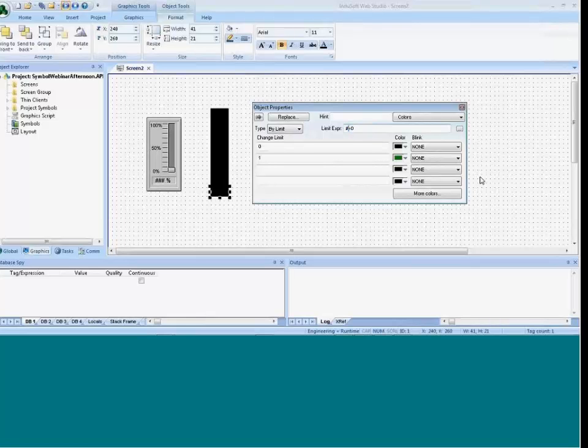So I'm going to put a pound sign in here, and then the name of the property. So in this case, to stick with some of the other ones that we have, we're going to call this tag name, and then a colon. And I don't have to have anything after that. So whatever I put into that value field during the properties configuration, it's going to replace this here and then compare it to whether or not it's greater than 0. So what I can do is copy this text and go through all of these.